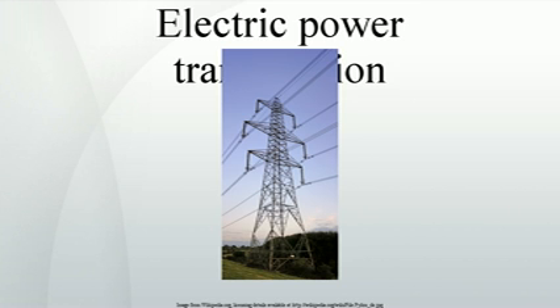The increase in voltage is achieved in AC circuits by using a step-up transformer. HVDC systems require relatively costly conversion equipment which may be economically justified for particular projects such as submarine cables and longer-distance high-capacity point-to-point transmission. HVDC is necessary for the import and export of energy between grid systems that are not synchronized with each other. A transmission grid is a network of power stations, transmission lines, and substations.